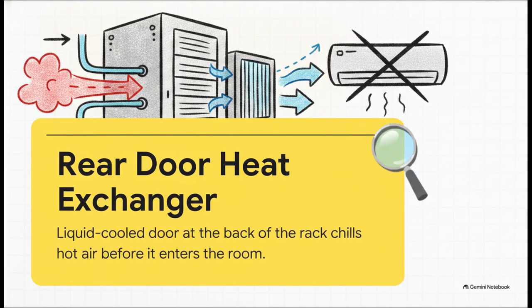And finally, the third option is the rear door heat exchanger, or RDH. This is basically your least disruptive method. If you don't want to run tubes of liquid directly to your silicon chips, you instead replace the back door of your server rack with a liquid-cooled radiator door. The traditional server fans still blow hot air out the back, but that air immediately passes through the chilled door, cooling it down before it ever even enters the data center room. It's a fantastic transitional step to drastically reduce your need for those giant room air conditioners.